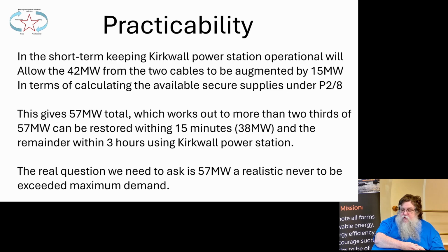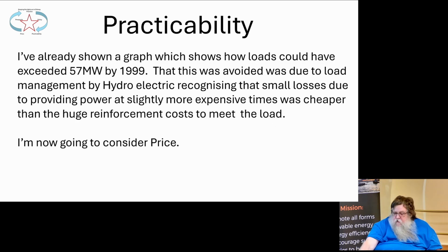The real question we need to ask is, is 57 megawatts a realistic, never to be exceeded maximum demand? I've already shown you a graph that showed how loads could have exceeded 57 megawatts by 1999. That this was avoided was due to load management by Hydroelectric, recognising that small losses due to providing power at slightly more expensive times was cheaper than the huge reinforcement costs to meet the load. So this was Hydroelectric, an integrated company who could take the balance and say, we're going to supply cheap rate electricity at an expensive time to customers in Orkney. It'll cost us £500,000 a year, and that's going to save us £50 million on a reinforcement. So all of a sudden they say, we're not going to spend the £50 million on reinforcement. We'll spend the £500,000 on supplying cheap rate electricity to customers at a loss, basically.